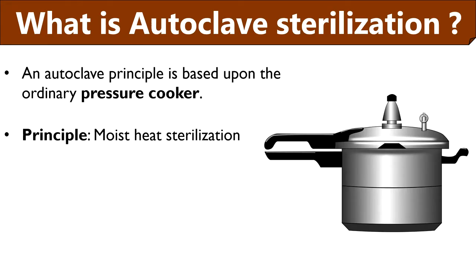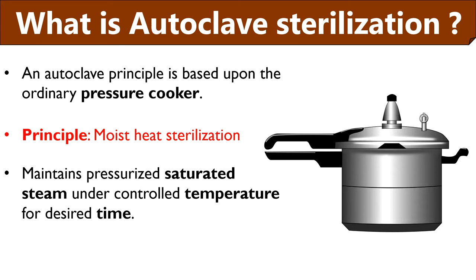Let us discuss what is autoclave sterilization. Autoclave sterilization has the principle similar to the ordinary pressure cooker. It produces high-pressure steam to destroy bacterial cells and fungal spores from different media, samples, equipment and glassware. As autoclave uses dry saturated steam, its principle is based upon moist heat sterilization that causes absolute denaturation and irreversible coagulation of macromolecules like enzymes and structural proteins of microorganisms. It maintains sterile environment by providing pressurized saturated steam under controlled temperature for desired time.